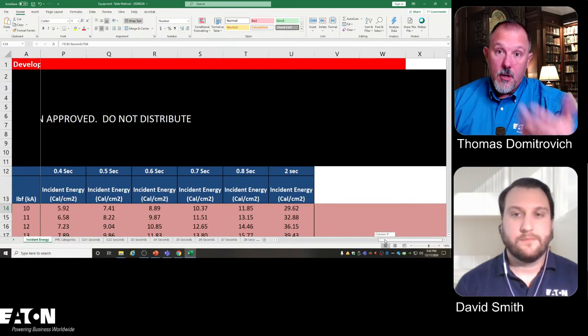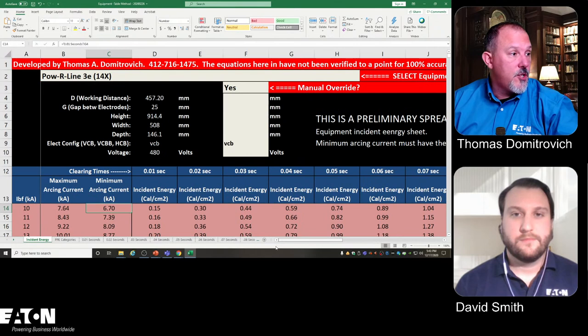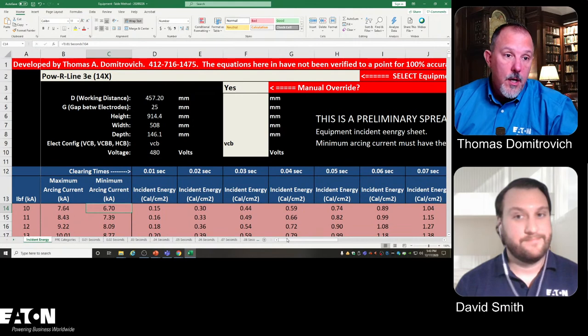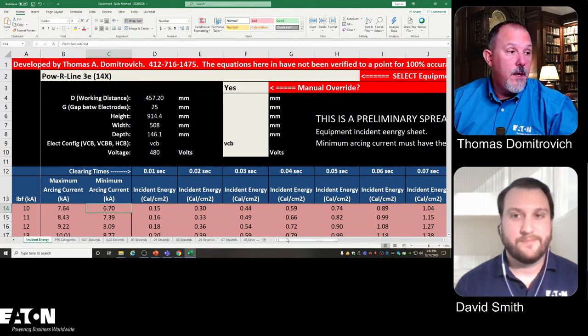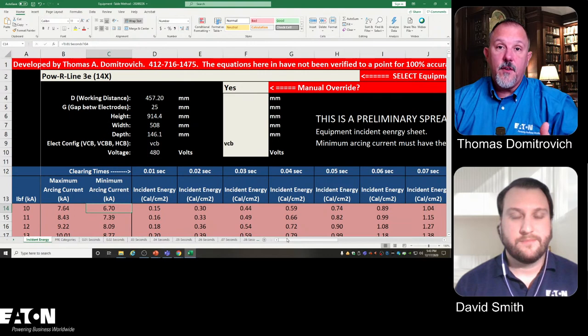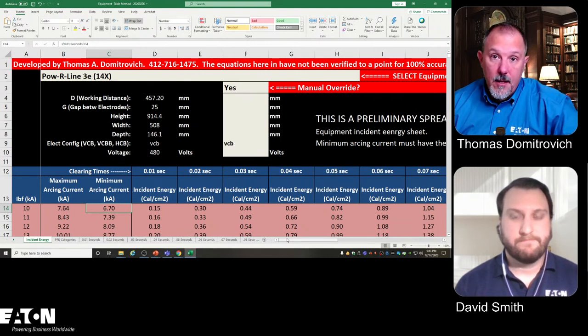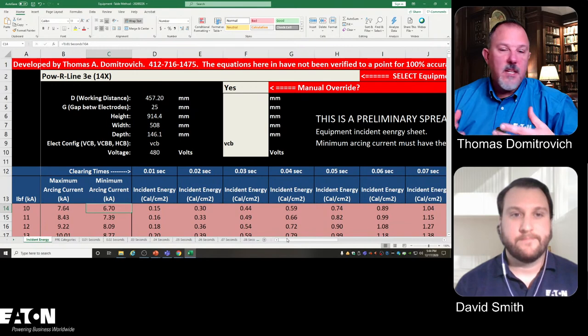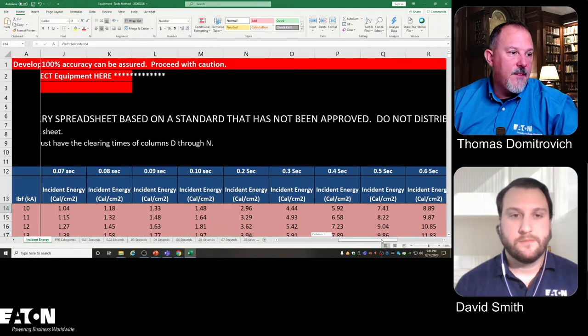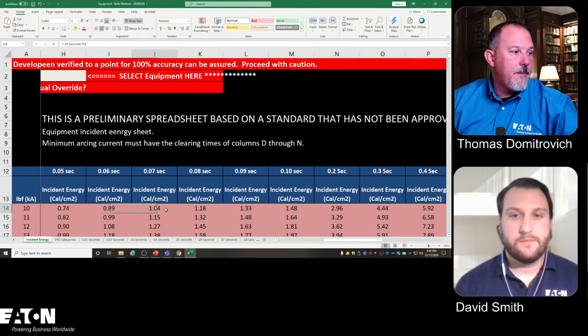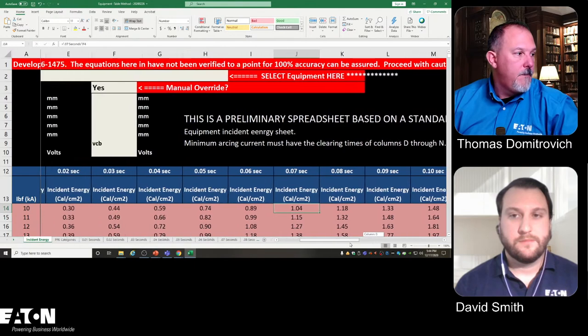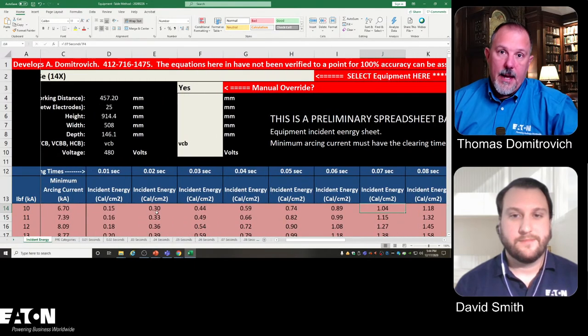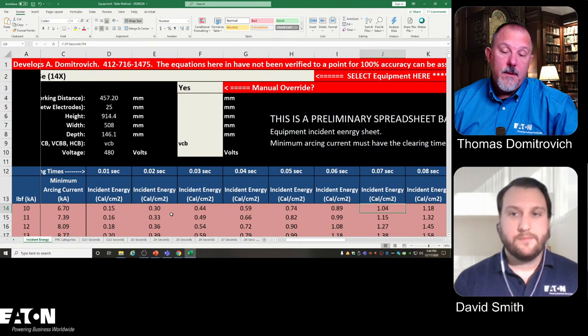And if I put an arc reduction method on, like say the arc reduction maintenance switch, which clears in about 0.02 seconds, I go from 29 calories to 0.3. So from a Tim Krauscher's perspective, and his question basically was, what's the difference? The difference could be huge, 20-some calories, 29 calories, right? So it depends on the clearing times. Now, if I'm in a short time delay and I have, say, 0.07 seconds, I take it from 1 calorie down to 0.3 calories, which isn't that much. 1 calorie, I mean, don't get me wrong, you don't want to experience a calorie either.